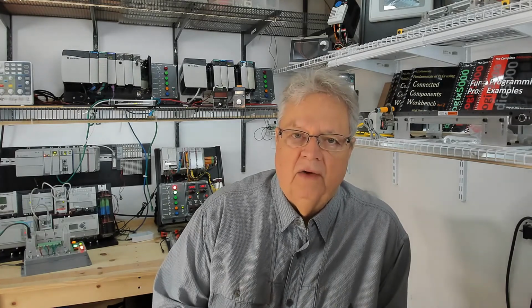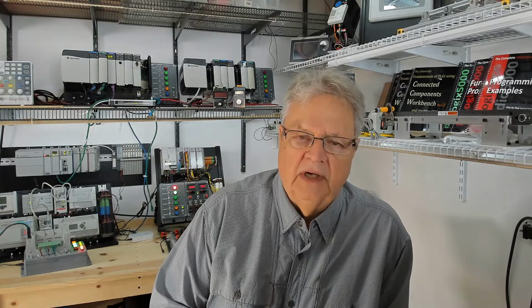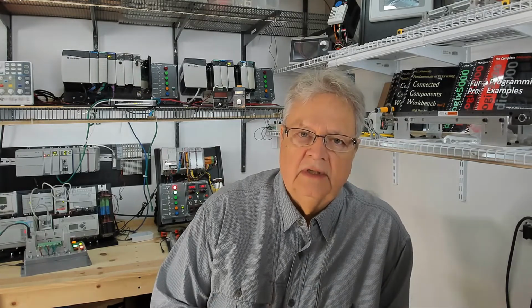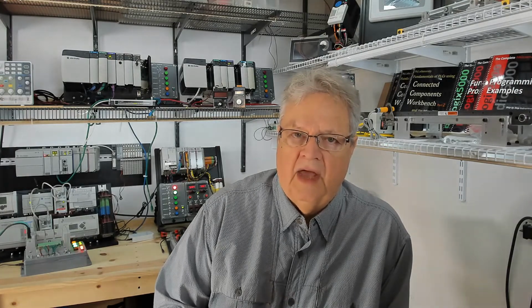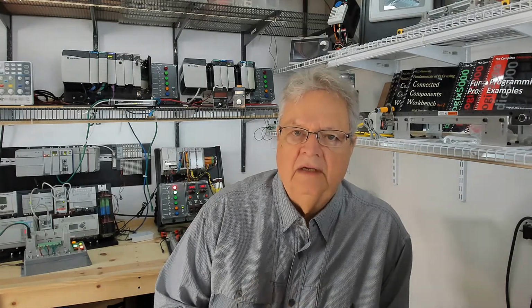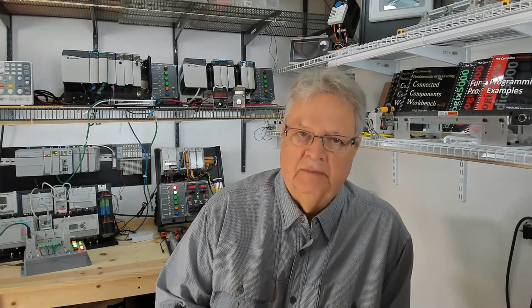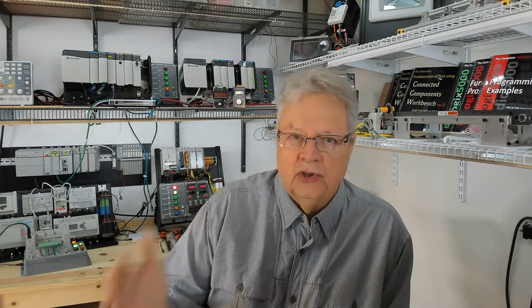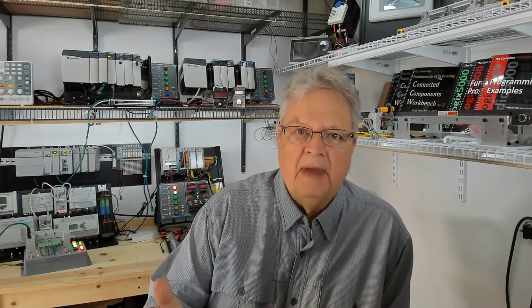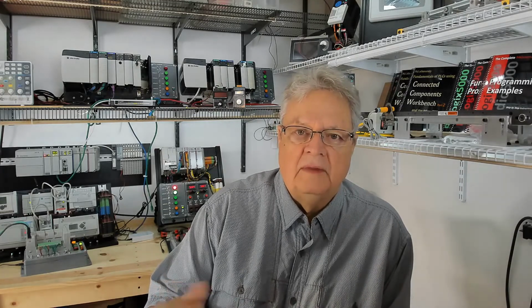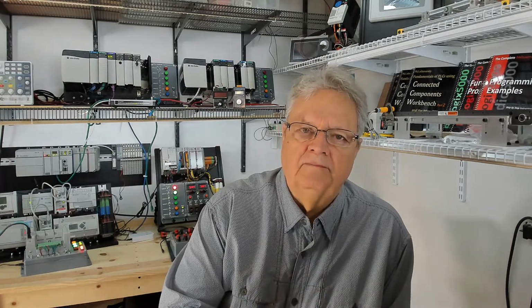Buffering IO is extremely important with the Logix engine simply because of the non-synchronous IO update process. With the active backplane, you activated a module on the backplane and then you did an update. If it was an input module, you turned on that module's input states went onto the backplane, and then the processor read it off the backplane and put it in a memory location.